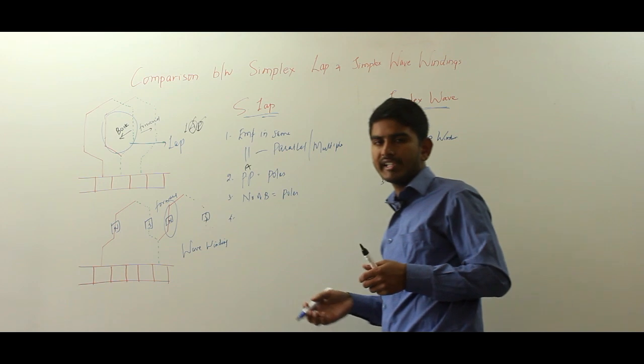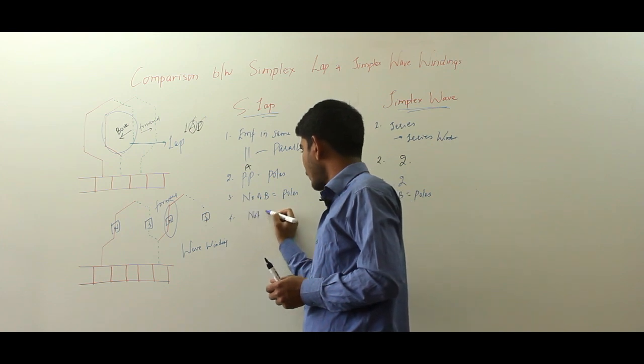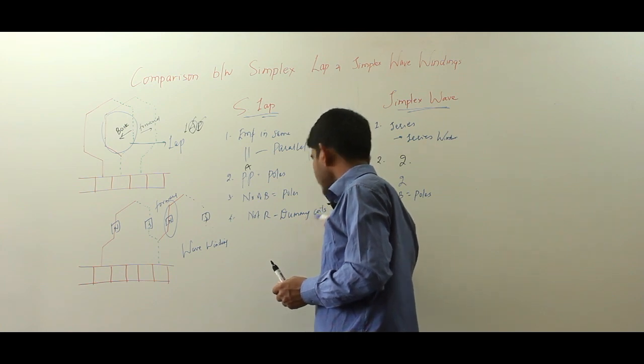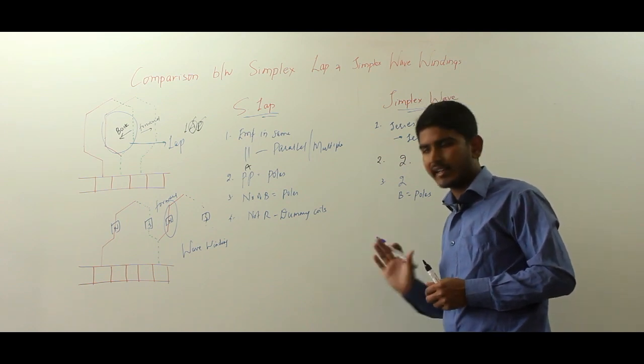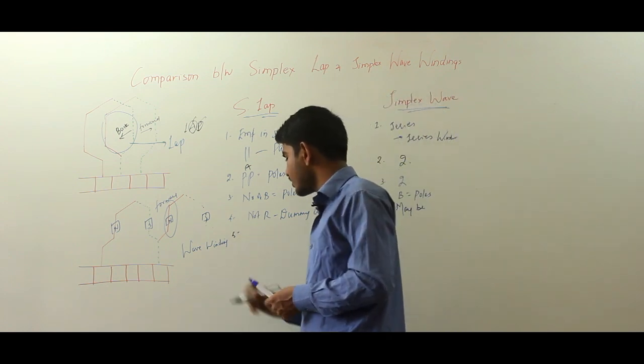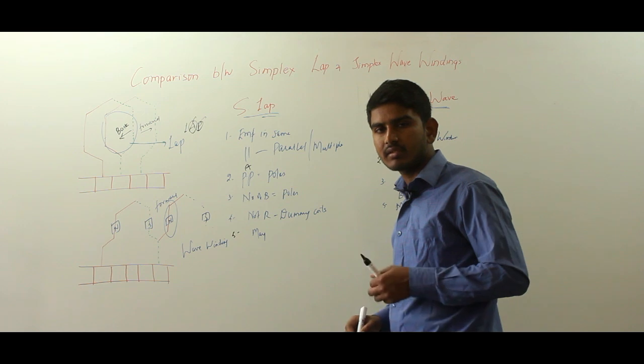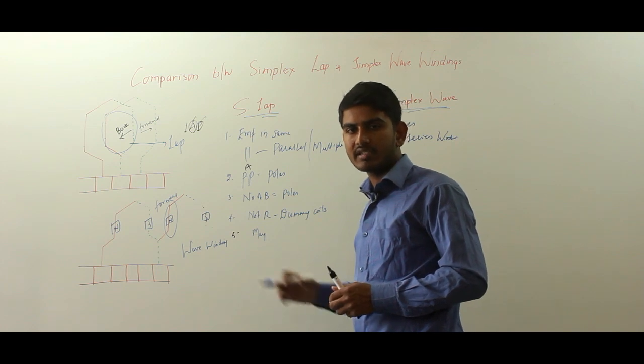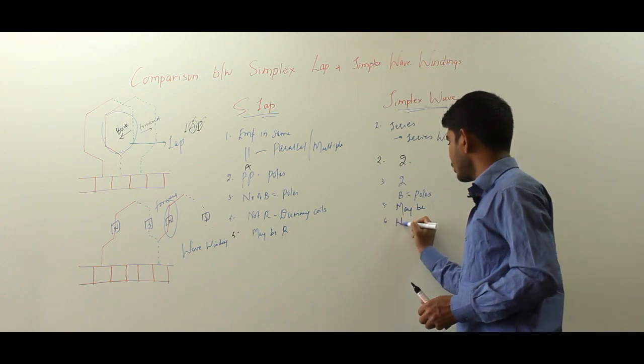The fourth difference involves dummy coils and equalizer rings. In simplex wave winding, dummy coils are not required. Dummy coils are inactive coils used to give mechanical balance to the machine. In lap winding, dummy coils may be required. Regarding equalizer rings — these are low-resistance copper rings connected to points to equalize potential difference and avoid circulating currents — equalizer rings may be required in lap winding but are not required in wave winding.